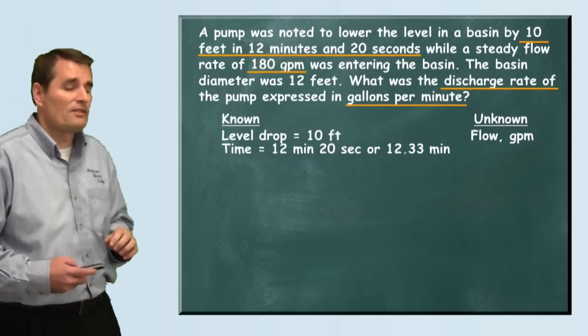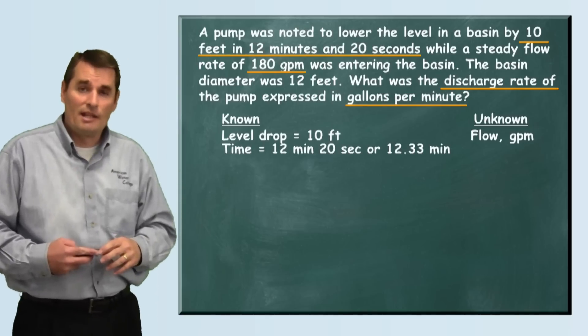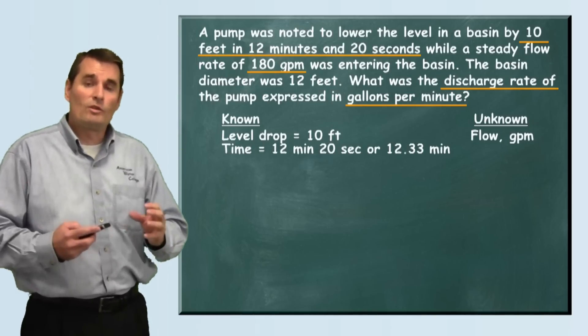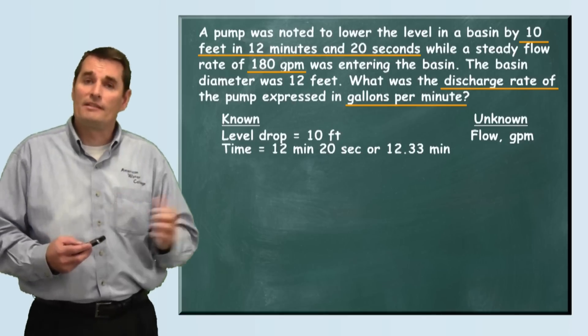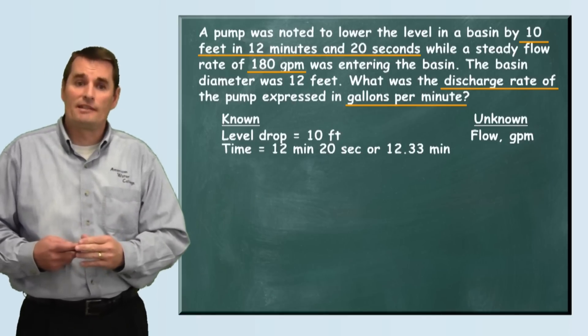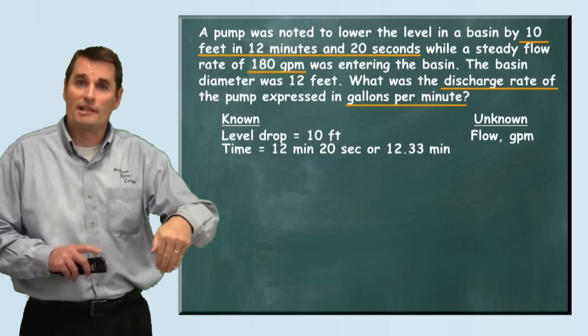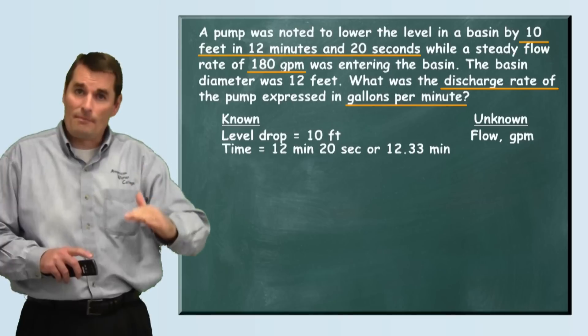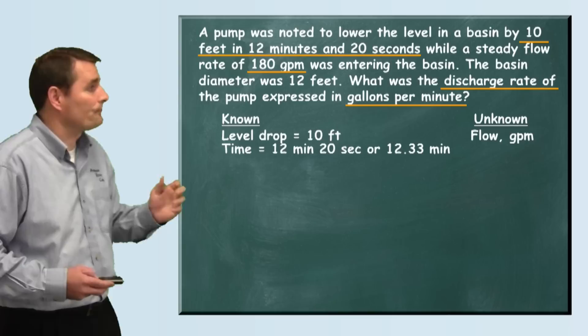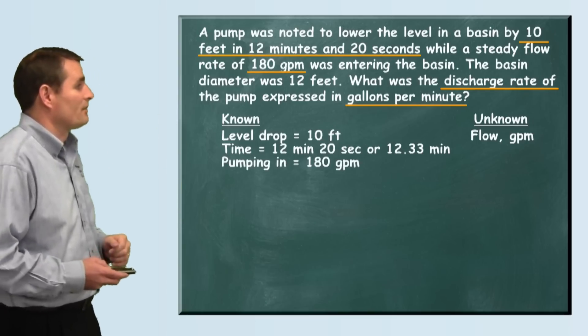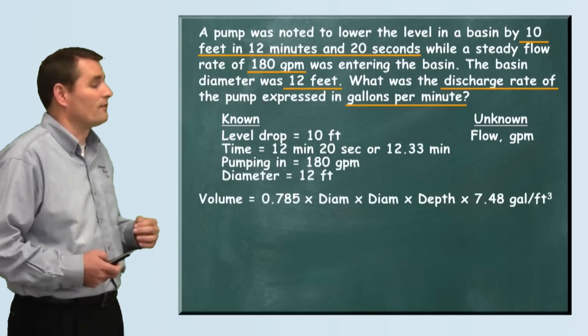We also see that there's 180 gallons per minute flowing into this basin. When we get to the end of our problem we're going to need to add in that 180 gallons per minute, because the pump discharging from this basin is pumping at a rate enough to overcome the 180 gallons per minute coming in and still drop the level 10 feet in 12.33 minutes. Our diameter is 12 feet, which we'll use in calculating the volume.